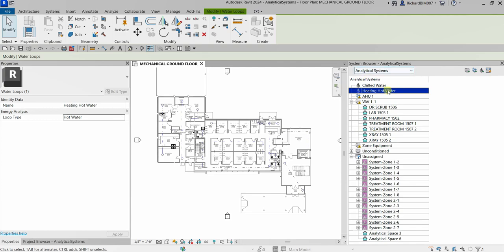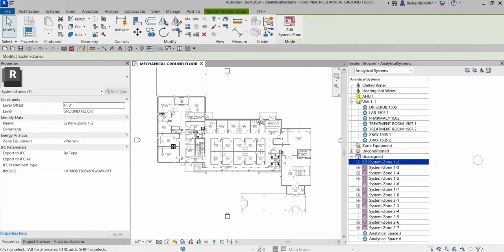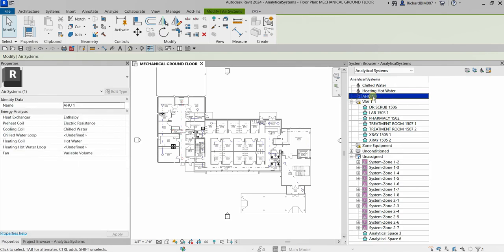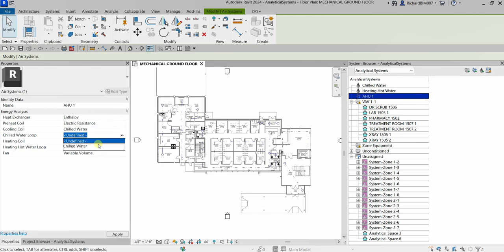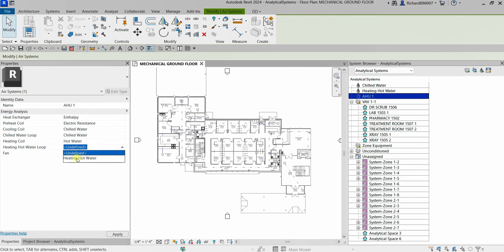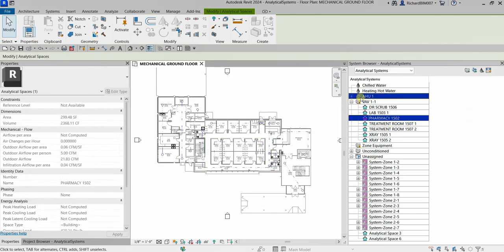Now we need to apply the chilled water and heating hot water loops to AHU1, our air system. Notice the exclamation point on AHU1 indicating something is missing. Select AHU1, click the drop-down for the chilled water loop and select 'Chilled Water,' then click the drop-down for the heating hot water loop and select 'Heating Hot Water.' Click Apply — the exclamation point is gone, meaning AHU1 is completely defined.